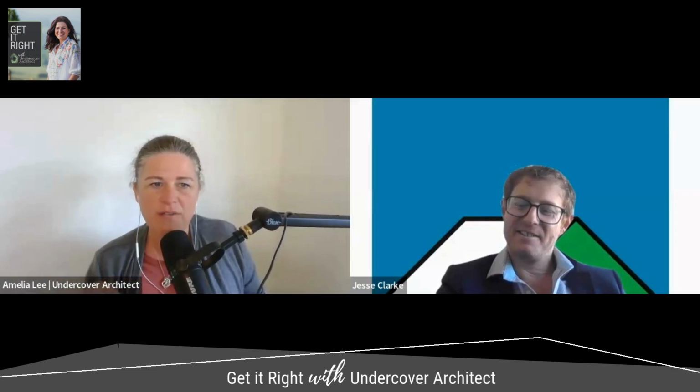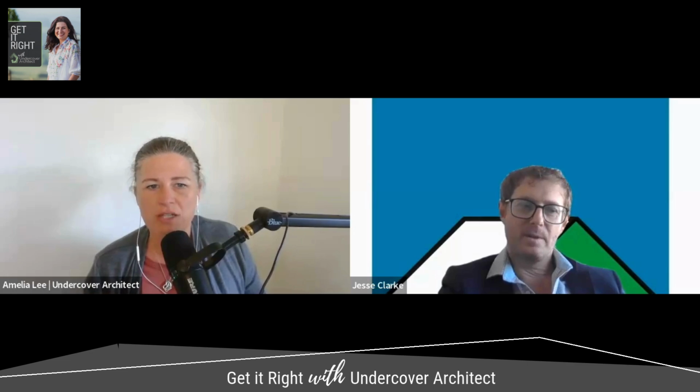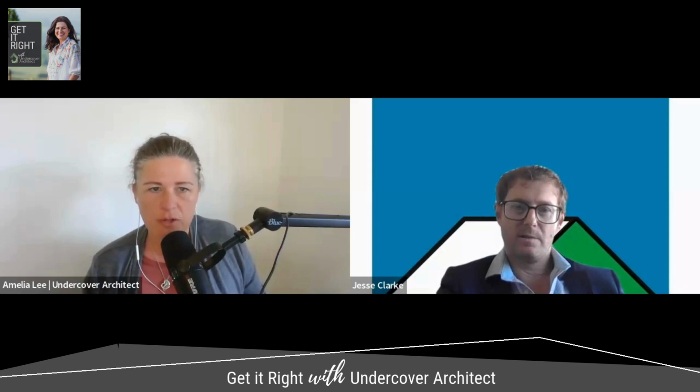And I wanted to dive into that because it says, and I'm going to read this out: The report begins by stating that this study outlines construction solutions to achieve low energy, healthy and durable housing for future generations. A desktop analysis using WUFI Pro software shows that in space-conditioned housing, the incorporation of intelligent air barriers, or IABs, on the inside of the framed wall assemblies in Australia will almost completely eliminate the risk of mould within walls in all climates except the tropics. And then you go on to talk about what to do in the tropics as well.